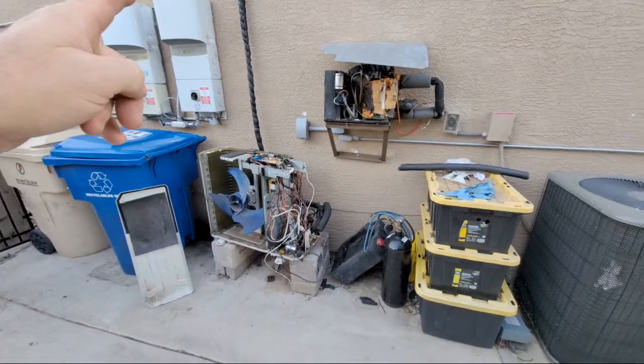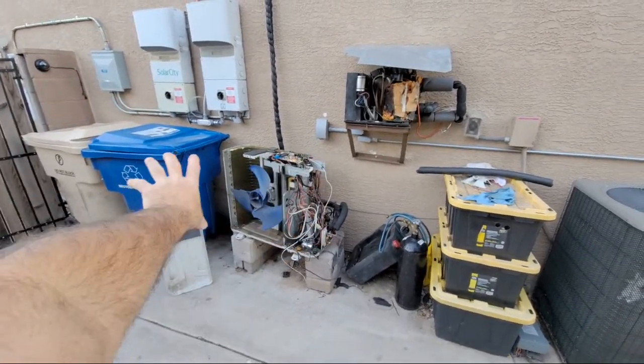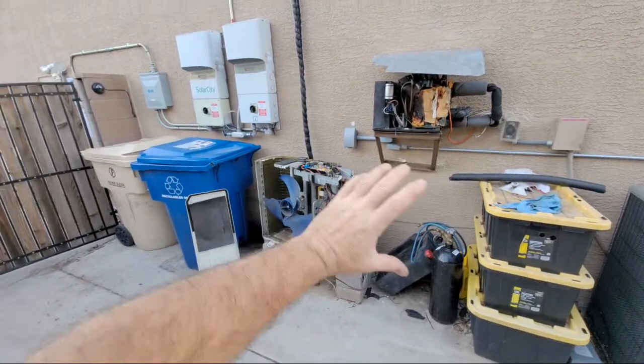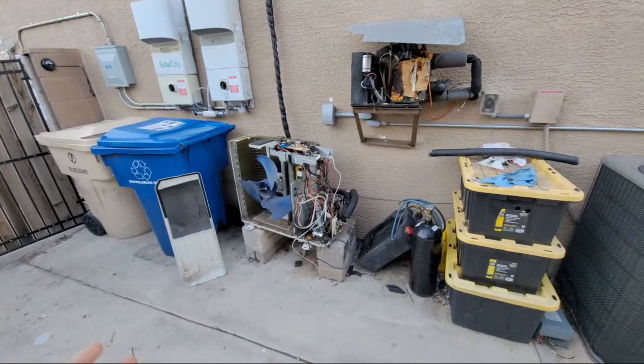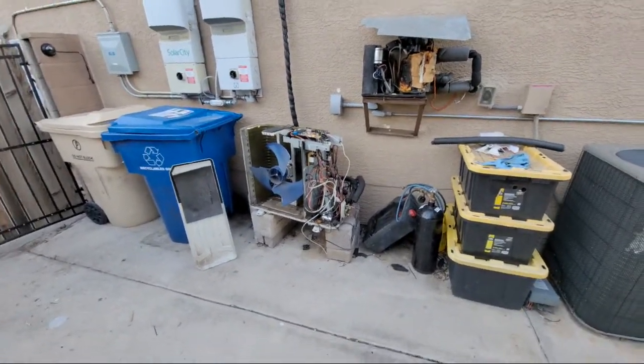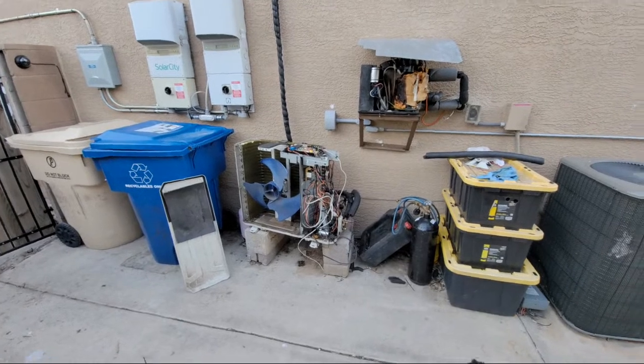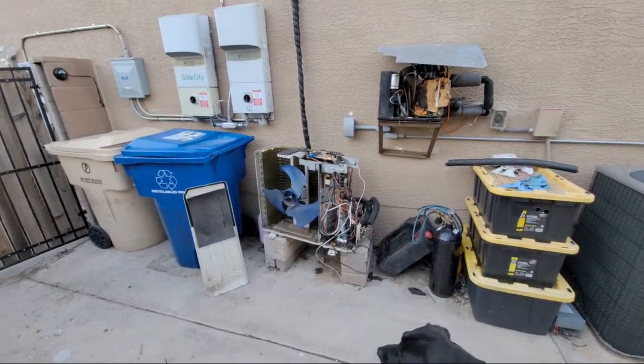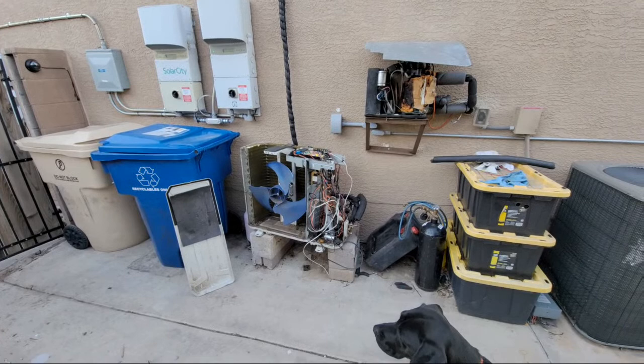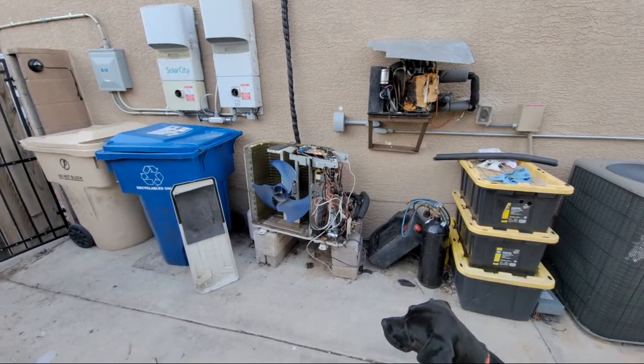It would cool the room like a mother. It would refrigerate the outside air really well, and frost up the coil because it ran so long with enough humidity in the air, especially in the mornings. So I've had to defrost it a bunch of times last week, and I'm just like, without changing the compressor, it just isn't going to work.